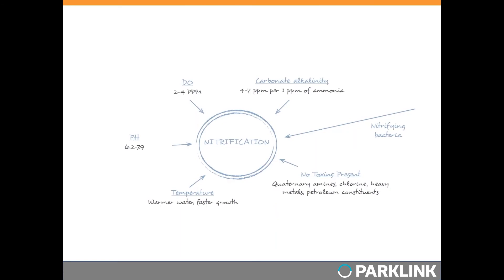We've touched on dissolved oxygen, carbonate alkalinity, and pH, and what happens when nitrifiers are lost through washout or toxicity. For plants with acute events where carbonate alkalinity, dissolved oxygen, and pH are all in good ranges, it's usually simple to get nitrification back by adding additional nitrifying bacteria. For plants with chronic issues, we work with them to figure out which parameter is causing the ongoing condition — it may actually be several different conditions.